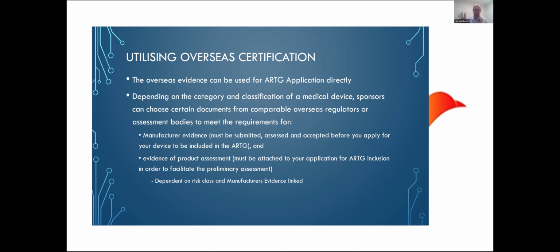So that's not just QMS, but also your product assessment. Now, it can get a little bit complicated, and there's very good guidance that the TGA have released, and it's been updated just recently, I think even at the start of this year, that provides you different scenarios. So, for example, if you rely on an FDA product assessment, you need to supply an MDSAP certificate as your manufacturer's evidence.